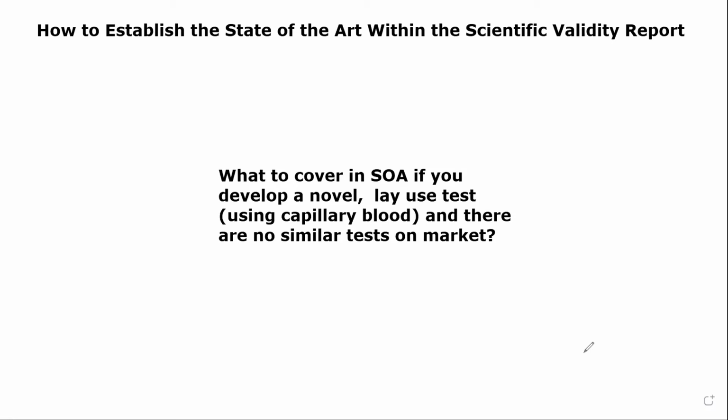So Sarah, I'm going to jump in and ask you to speak just another minute more about the importance of providing a clear justification to the notified body that this is your approach and this is why, and this is how we're going to deal with our problem. Yes, so within the templates that we've developed for the SVR and within the SOA section, we very clearly describe the decisions that were made early in the process with regards to the PICO terms, our patient population, and all of the different alternatives that are out there.